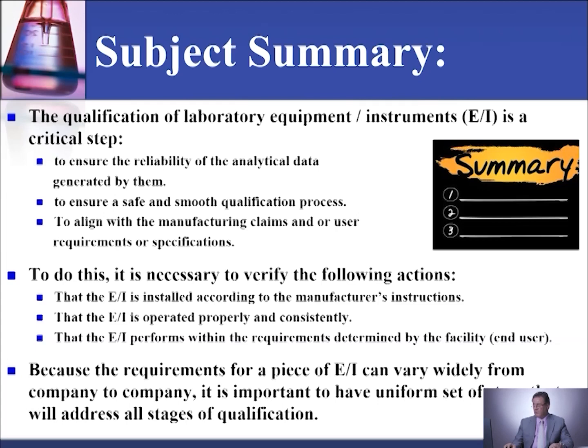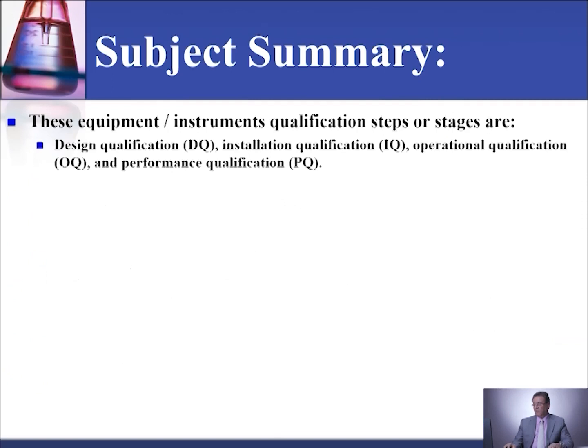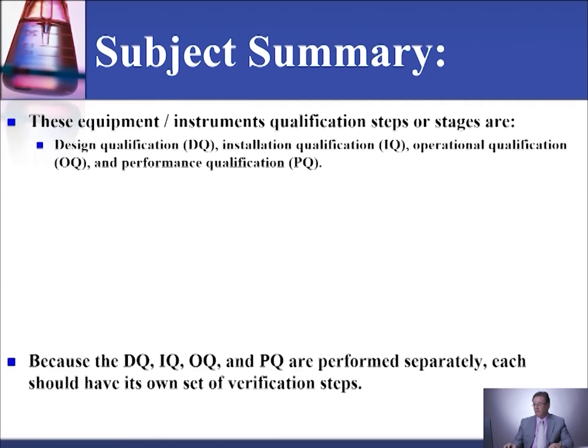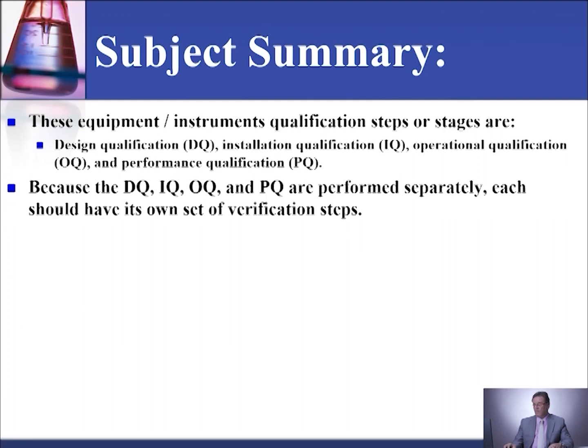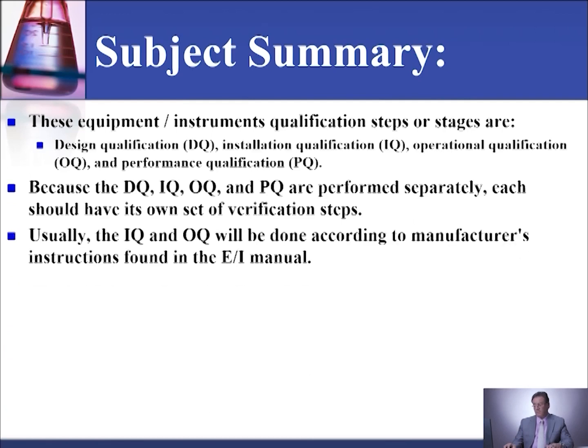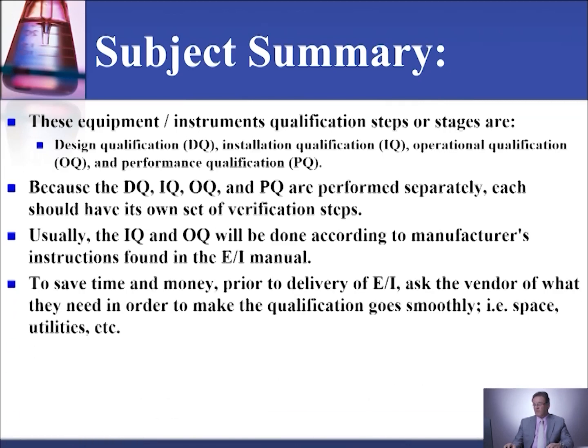It is important to have a uniform set of steps that will address all the stages of qualification, like I described to you in these three lessons. These equipment and instrument qualification steps or stages are DQ, IQ, OQ, and PQ. Because the DQ, IQ, OQ, and PQ are performed separately, each should have its own set of verification steps, like I showed you and described to you. Usually, the IQ and the OQ will be done according to the manufacturer's instructions found in the equipment or instrument manual. To save time and money, prior to delivery of the equipment or instrument, ask the vendor what they need in order to make the qualification go smoothly, like the space and utilities.